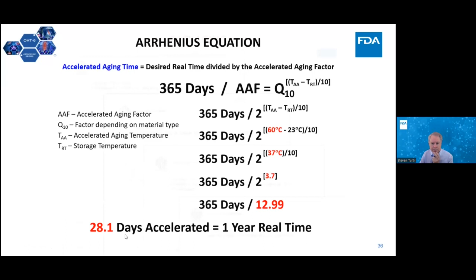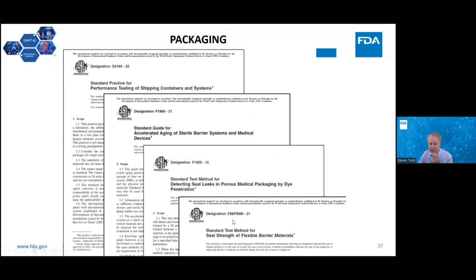Again, this is the standard we were just talking about, ASTM F1980. What we're going to consider now is testing seal strength. This is the bottom one, ASTM F88 or F88M. And seal strength, whatever you choose to be your final acceptance criteria, should be scientifically justified. There is no one single standardized acceptance criteria in a standard anywhere that is FDA recognized. There's one ASTM standard that does specify one, but we don't recognize that.